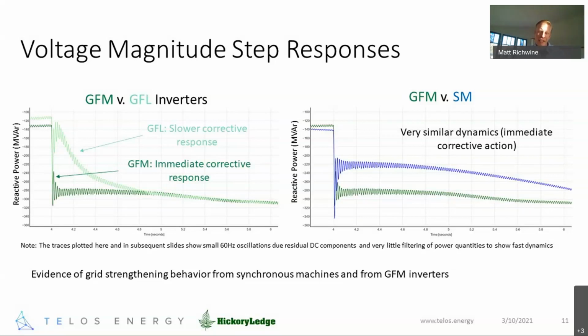One of the things that really jumped out here is that in comparison and contrast, the GFM in these short time frames has a dynamic behavior that is more similar to a synchronous machine than it is to a grid following inverter. To me, that is the evidence of grid strengthening behavior. The grid strength that we conventionally have relied on today from synchronous machines is possible to come from grid forming inverters because of this type of behavior. Now, this is not to say they're a one-to-one substitute, and we'll talk a little bit more about that.